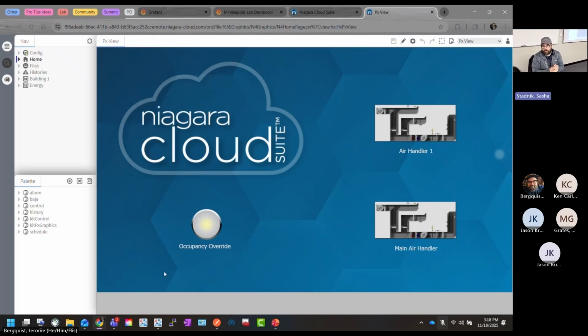You can connect remotely, you can open it there. You can run the BACnet discovery because BACnet Device Manager works, there's a web view for BACnet Device Manager. You can discover it, bring it in, add the points, add the graphic, modify the schedule, whatever you need to do, all through Niagara Remote.